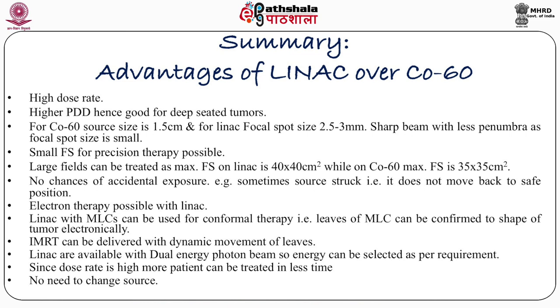Large fields can be treated with linac, as the maximum field size on linac is 40 by 40 centimeters, while in cobalt-60 the maximum field size is 35 by 35 centimeters. There are no chances of accidental exposure — for example, sometimes the source gets stuck in cobalt-60 and does not go back to the safe position. Such situations do not arise in linac because there is no natural or artificial radioactive source inside. Once we switch on the machine, radiation starts coming out, and as we switch off the machine, radiation stops.